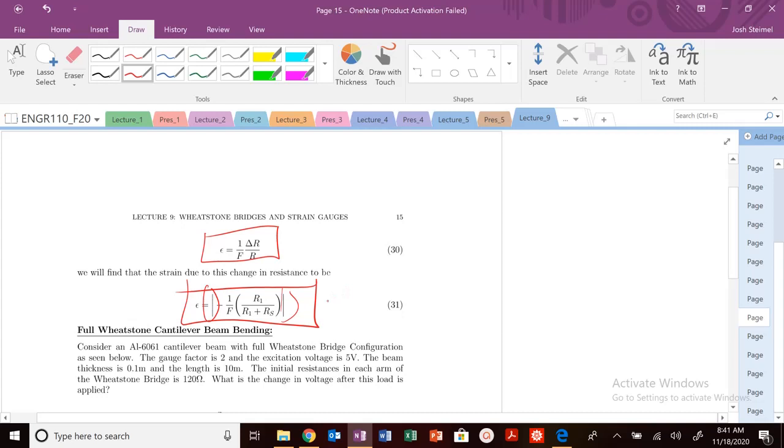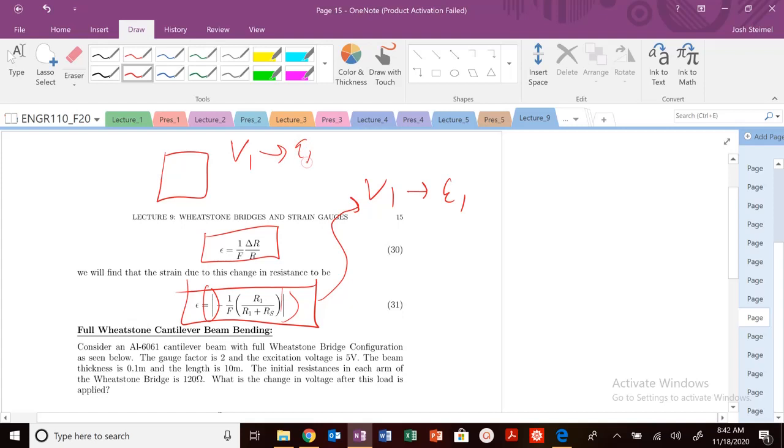Now, when you read a problem, typically you say once we close this shunt resistor, we'll read like a voltage V1, and that's going to correspond to strain epsilon 1. Then you'll do your operation, we'll either pressurize our pressure vessel, we'll pull our material, so when we close that shunt, when there's no load applied, we have a voltage 1 corresponding to a strain 1. And that strain is just this strain right here.